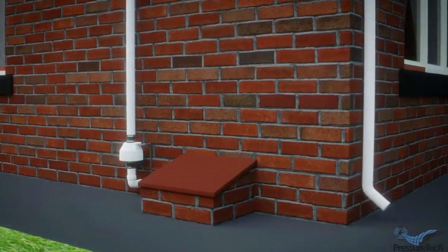Some of the houses that need to be mitigated have soil that is not porous — it's very dense. So that presents a problem for a radon mitigation system, because sometimes it's very difficult to move the air through that dense material. Therefore you need to do several things to be able to extend that pressure field. It's all about extending the pressure.